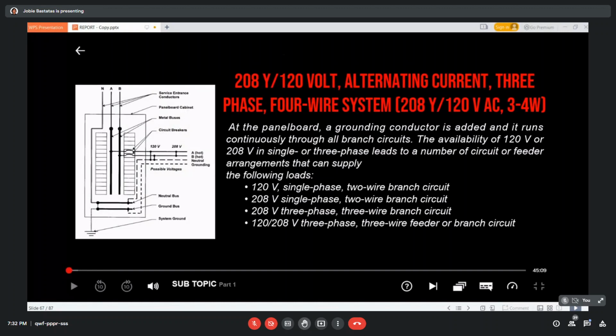Next is the 208/120 volt alternating current three-phase four-wire system. The 208/120 volt alternating current three-phase four-wire system is an older electrical service found in small commercial buildings, office buildings, schools, and high-rise buildings. It is not used very often in industry because a 480 volt system is more economical for large motor loads. At the panel board, a grounding conductor is added and it runs continuously through all branch circuits.